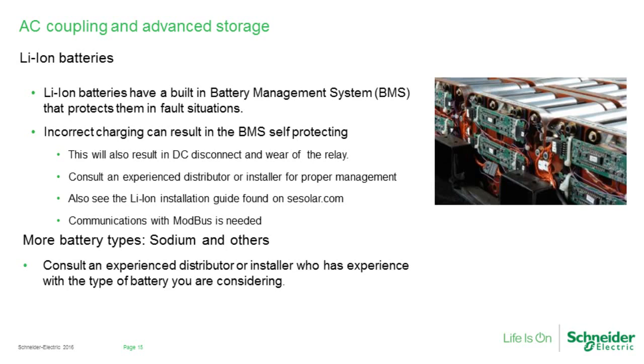See the lithium-ion installation guide at sesolar.com, which will give you some guidelines. If it's a newer solution or a newer lithium company, really find out if communications with Modbus is going to be needed. Very likely the battery management system will need to talk to the Schneider XW Plus or Connect SW to make sure we're properly managing the output current of that system and not accidentally overcharging those batteries. There are, of course, a lot of other advanced technologies out there, and the general recommendation is to have a conversation with the battery manufacturer about how they're going to manage or what they're going to need with that system.